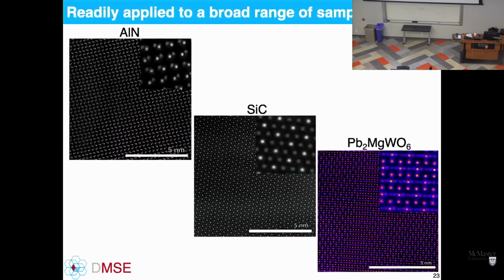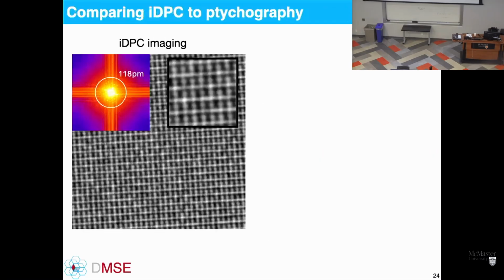Now, as I said, we can readily apply this to a broad range of samples: aluminum nitride, silicon carbide, lead magnesium tungstate. Atomic number doesn't matter. Thickness of the sample limits out at about 40 to 50 nanometers or so, depending on the atoms present. But the technique works, it's reproducible, and we've gotten fairly routine acquisitions at this point.